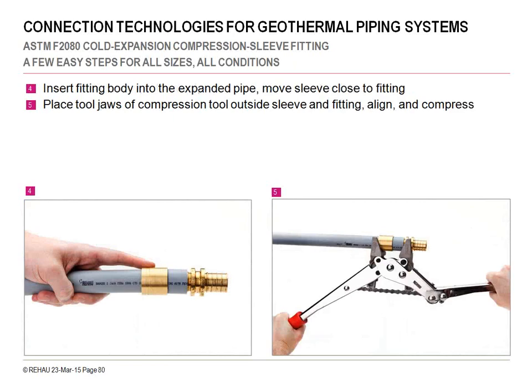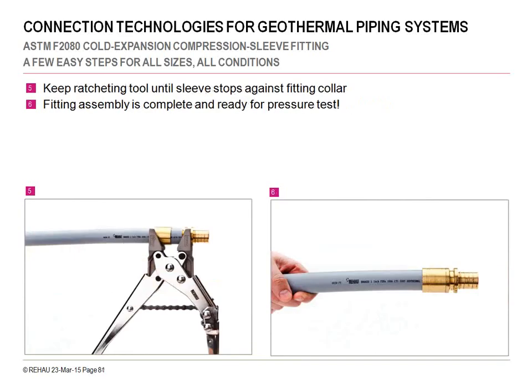You can see in image 4 the fitting has been inserted. And if that sleeve wasn't pulled up, I just want to mention that after about 10 minutes, it would be extremely difficult to pull that fitting out of that PEX-A pipe, because I mentioned that PEX-A pipe is a thermoset. What's happening is that pipe is trying to come back to its original extruded ID dimension. So considerable force is being applied to that fitting before the sleeve is pulled up over the pipe and the fitting. The second step is a ratchet that's geared. The ratchet, as you can see, has jaws, and we're going to ratchet that sleeve up over the pipe and the fitting, and you can see the finished connection in slide 6 there.